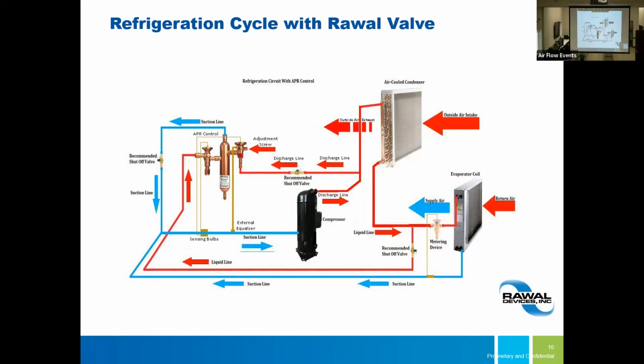Downside to those is that it doesn't tell you what the humidity is in the space at all. It doesn't know. It's just looking at the temperature of the suction line and the liquid line and modulating accordingly. It doesn't know if it's real humid or not, right? Right. Yeah, you need a combination humidistat, thermostat in the space, and as long as the unit's running, it'll just operate off pressure. You just need to trick the unit into continuing to run based off the fact that it's too humid, and you're good to go because there's no other controls.